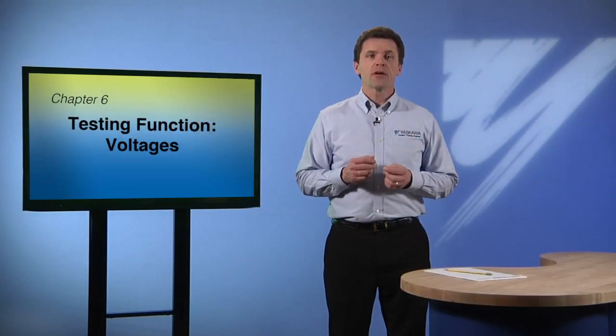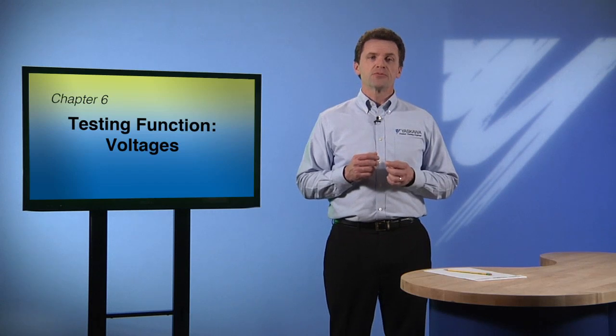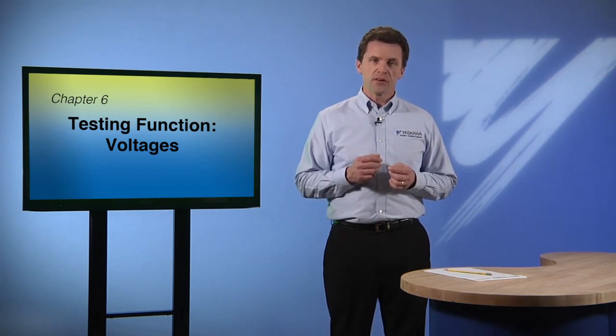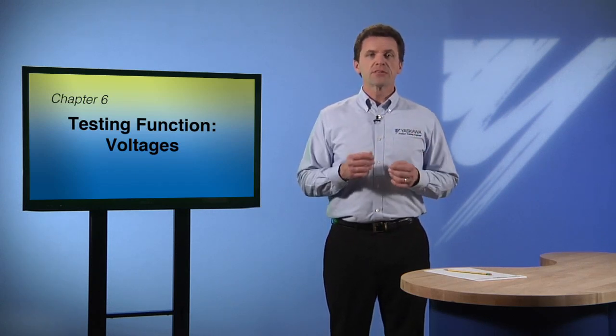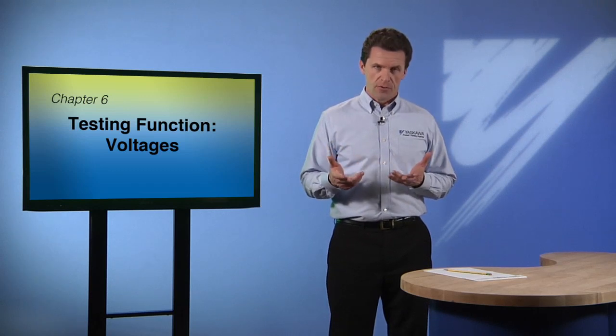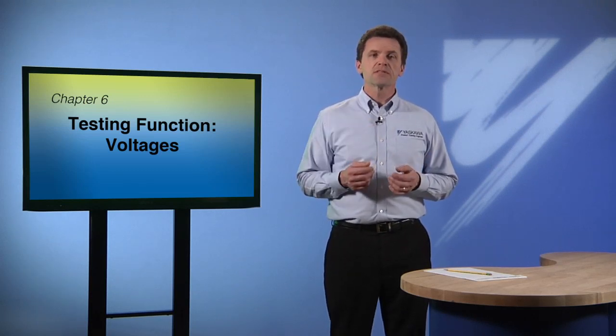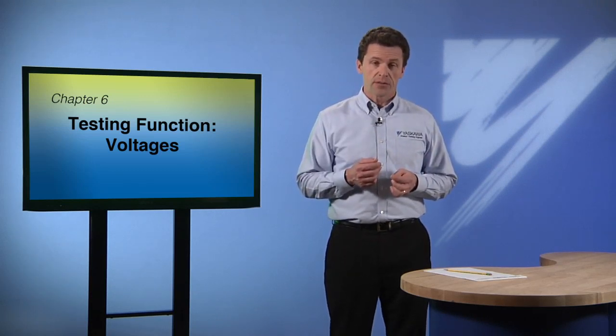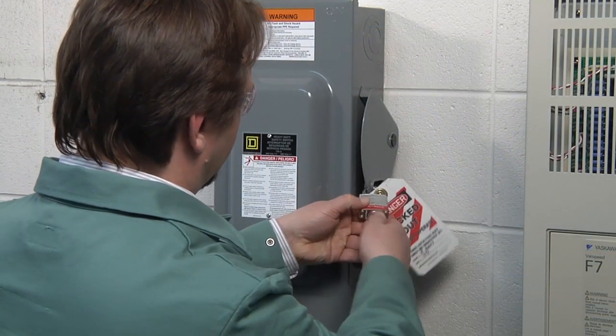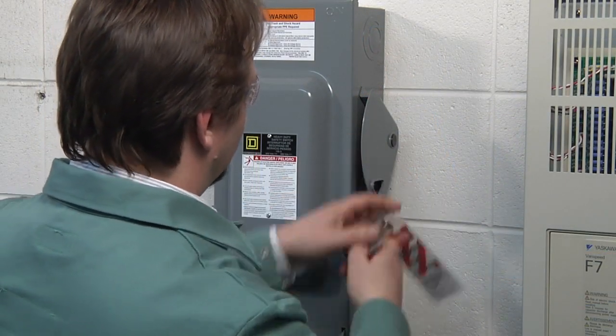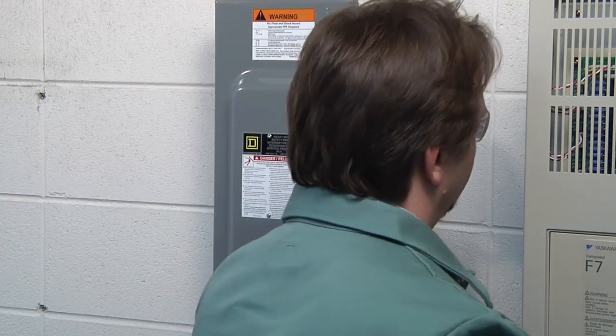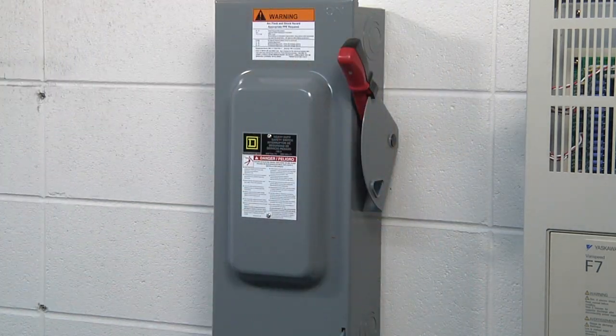Now we've come to the point where we can prepare to power up the drive and the bypass to run a function test. If the motor is attached to a fan or to some other mechanical system, make sure that the system is ready to safely operate during the test. Put on your safety equipment, remove the lockout-tagout protection, and power up the system.